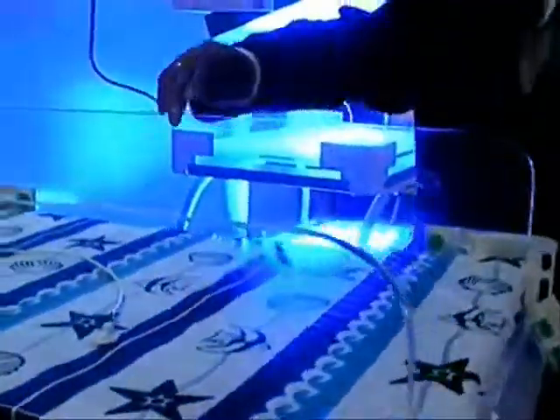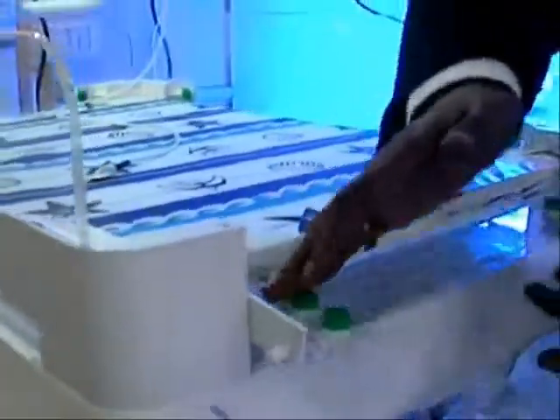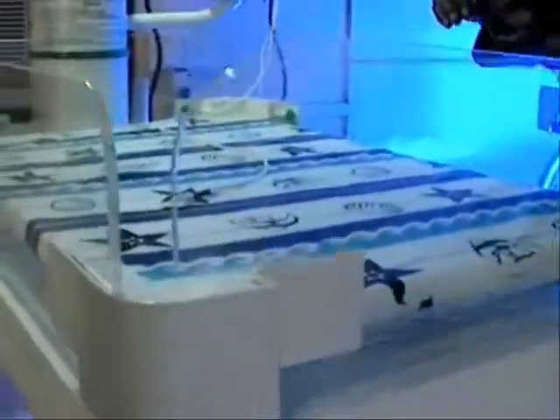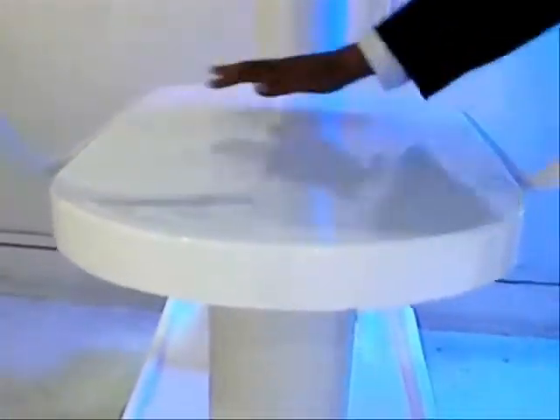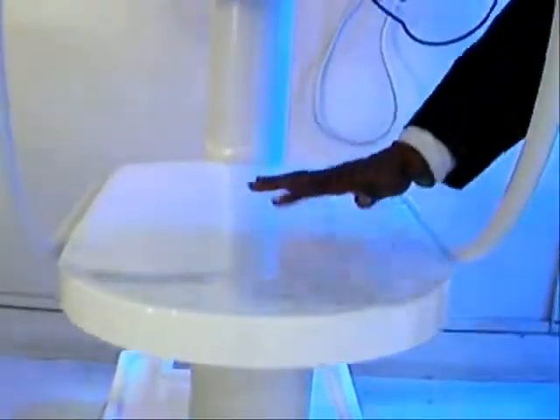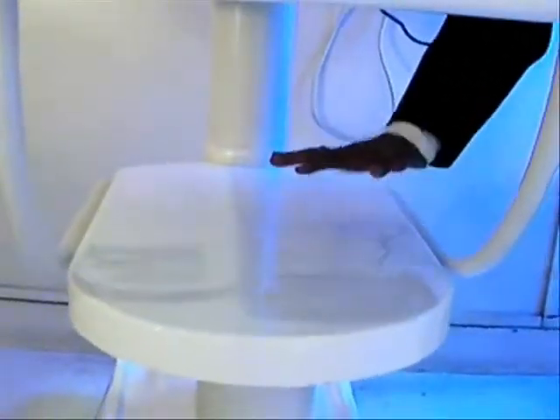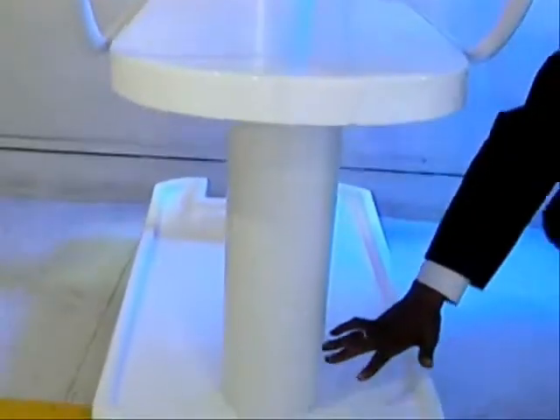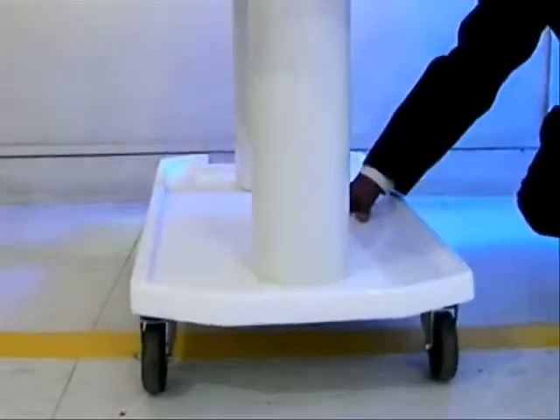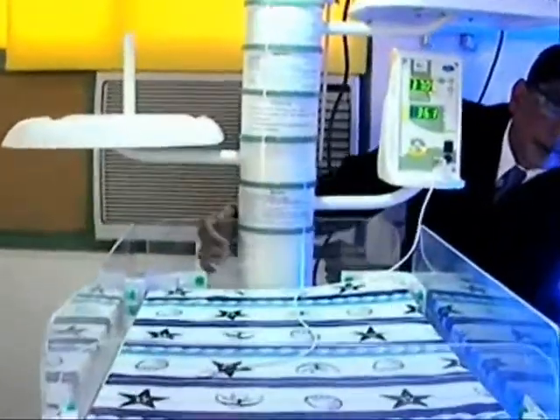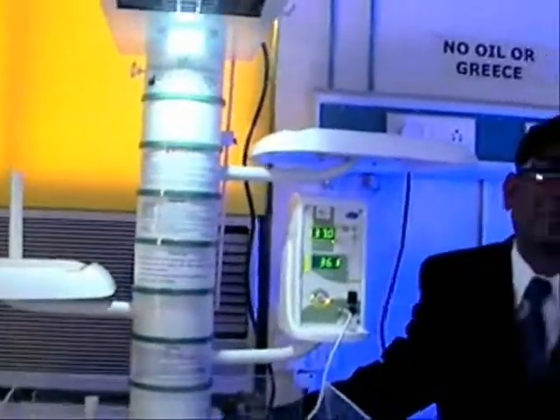Plus other small things, like we have drop-down access panels. If you want to fumigate, just remove these 2 screws and this entire thing comes out. You can just go and fumigate and clean it. Plus another thing is that the baby bed is made transparent from here, so you can even place it under surface phototherapy. And this is a tray where either you can keep an under surface phototherapy, or even the baby related material or the resuscitation material, whatever you require. And this is another storage that can be used if you need it. Above all, if you look at this machine, it's absolutely sturdy. Nothing goes wrong with this machine, and we always say minimum 15 years of life for this machine.